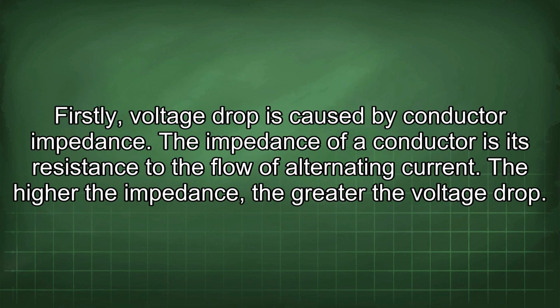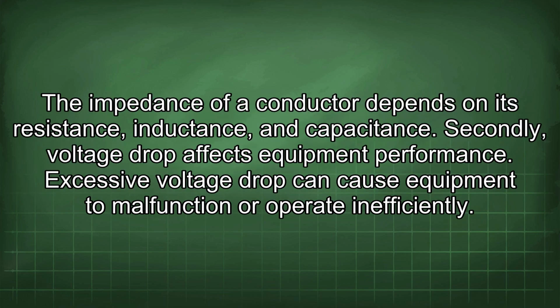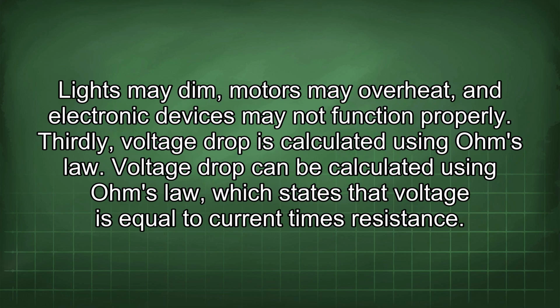Firstly, voltage drop is caused by conductor impedance. The impedance of a conductor is its resistance to the flow of alternating current. The higher the impedance, the greater the voltage drop. The impedance of a conductor depends on its resistance, inductance, and capacitance. Secondly, voltage drop affects equipment performance. Excessive voltage drop can cause equipment to malfunction or operate inefficiently. Lights may dim, motors may overheat, and electronic devices may not function properly.